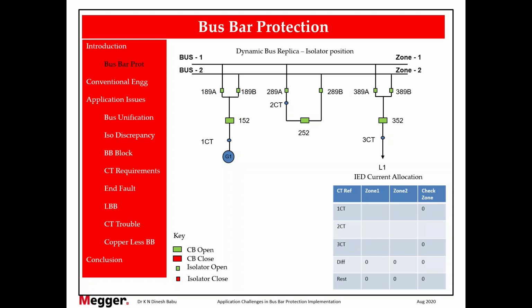Now we have to find which CT is going to read in which bay, which zone. So 1 CT, is it there in zone 1? It will not be there because the isolator is open. Is it there in zone 2? No, because 89B is open. The same thing repeats. So you can see no CTs are read in any of the zones. And what we have here is the differential and restraint formula. The formula would be simple vector addition or subtraction. Vector addition is the modern algorithm which we are using in numerical relay. So this will be the difference between all the currents shown here. And for restraint current, for our discussion, let us assume the maximum current principle, easy to calculate. So whichever current is maximum in this, that would be read as restraint current.